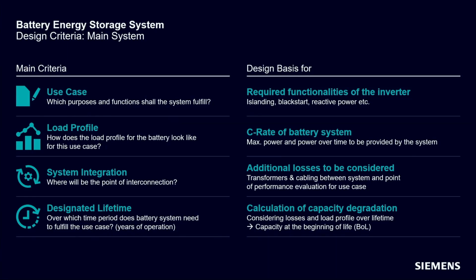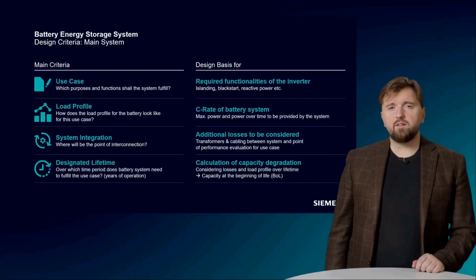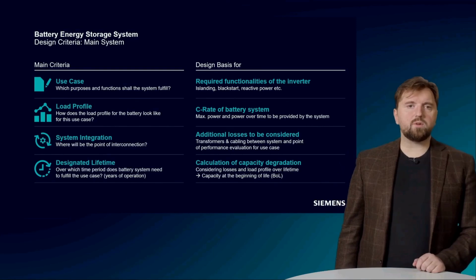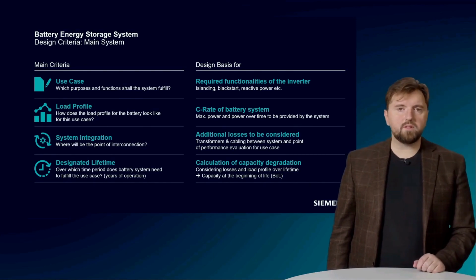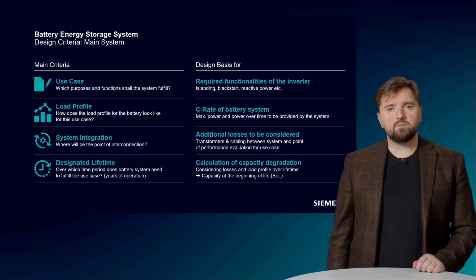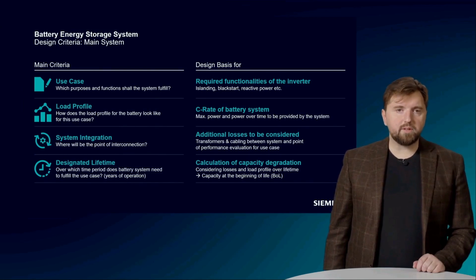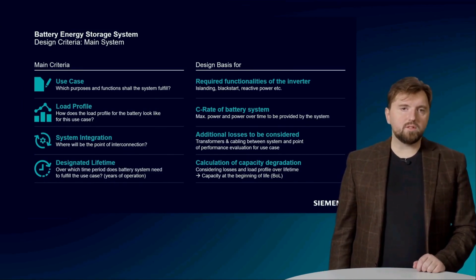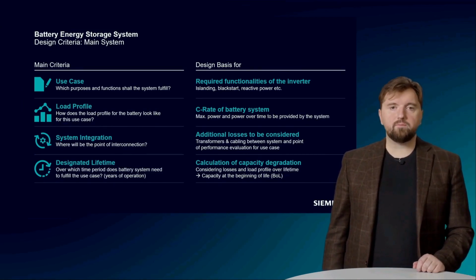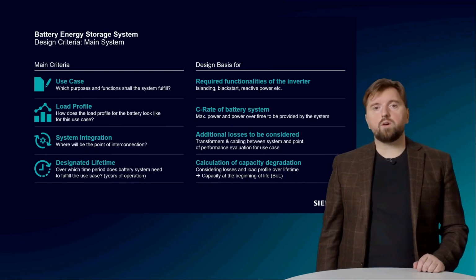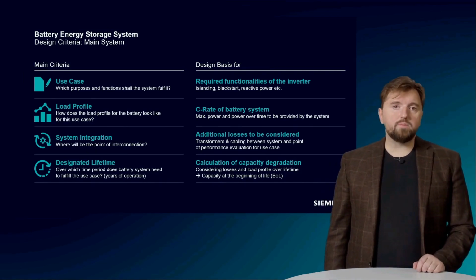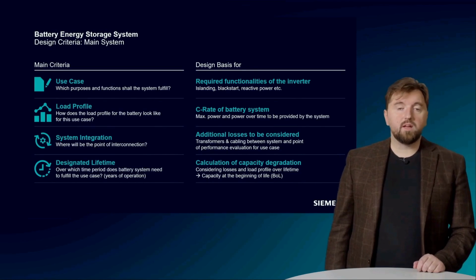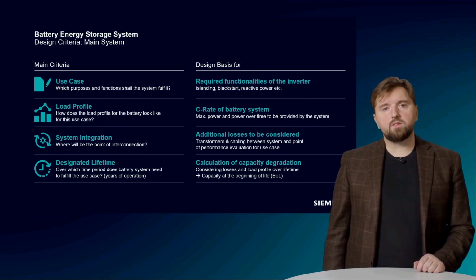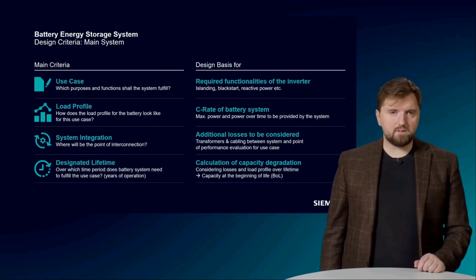How does the battery's load profile align with its use case? This will help in coming up with the C rate of the battery system. High C rates are typically used for applications that require large amounts of power over a short period, like frequency regulation in the grid. Lower C rates are used for applications that require steady power over a longer period, like load shifting. An important question to ask is also where will be the point of interconnection for the BESS. This is a relevant aspect as it will determine any additional losses that should be considered.